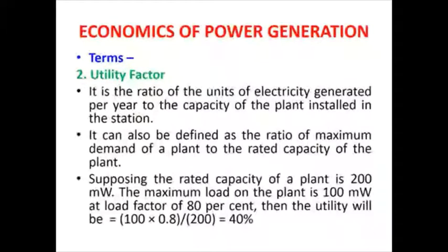So how do we calculate the utility factor? Just see the given values. Rated capacity is 200, maximum load on the plant is 100 megawatt, load factor is 80%. Therefore utility factor will be 100 into 0.8 divided by 200, that is 0.4. So the utility factor becomes 40%. What does it mean? It means that the installed capacity is large and only 40% of it is demanded from commercial, residential or industrial systems. So the utility factor is calculated in this way.